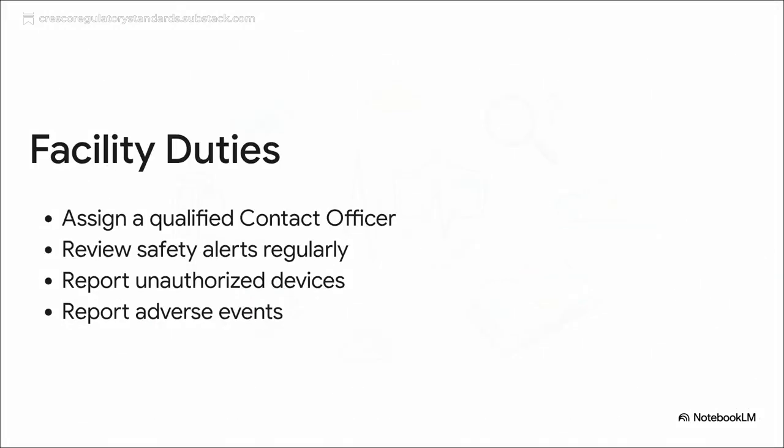And speaking of healthcare facilities, they are literally the final secure link in the chain of safe medical device use. They have super strict responsibilities. Every single facility must assign a qualified contact officer to act as the direct liaison with the SFDA. This officer has to regularly review safety alerts and make sure corrective actions actually happen on the ground. Plus, facilities are legally bound to report any unregistered, fraudulent, or unauthorized devices, as well as all medical device-related adverse events, straight to the NCMDR platform.